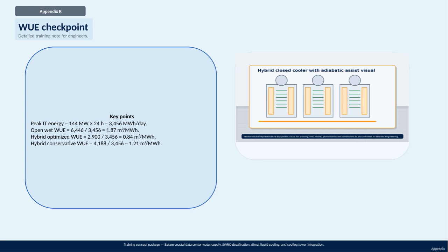Using this baseline, we see the open-wet WUE ratio is 1.87 cubic meters of water per megawatt hour, reflecting the water intensity without optimization. When applying a hybrid optimized approach, this number drops significantly to 0.84 cubic meters per megawatt hour, showing substantial water savings through integrated cooling and desalination techniques. The hybrid conservative scenario sits in between, at 1.21 cubic meters per megawatt hour, balancing water use efficiency with operational conservatism. These metrics are crucial for understanding how different strategies impact overall water consumption and efficiency in large-scale data center operations.